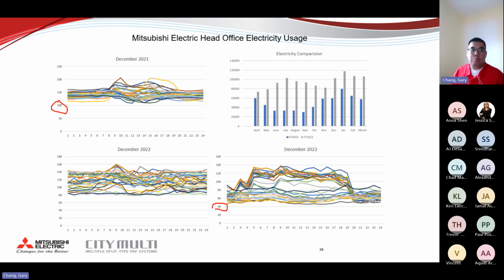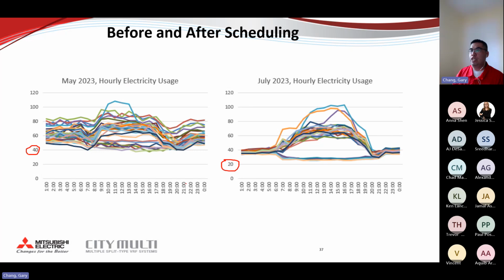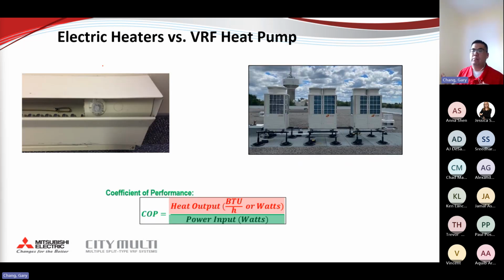Cooling is pretty obvious for many things — first, the weather is constantly changing, and with a 30-plus year old fixed speed compressor versus an inverter-driven compressor, the VRF system helps accommodate changes in load as well as outside air temperature while providing comfort. In winter though, keep in mind we have electric heaters versus VRF heat pumps, which is where coefficient of performance comes in. Electric heaters usually have a COP of 1, whereas VRF can have a COP of 2, 3, up to 4 in certain cases, depending on load. That's where COP comes into play.